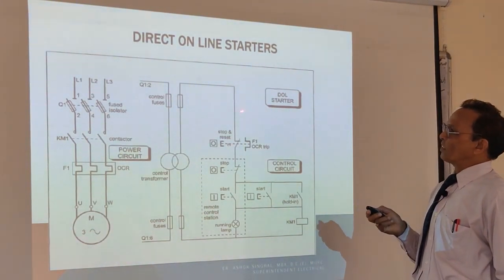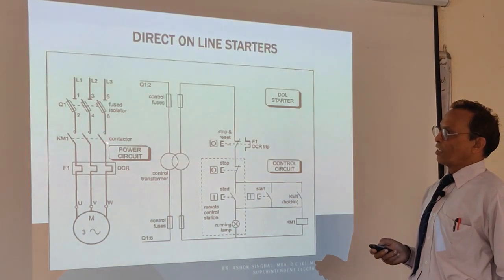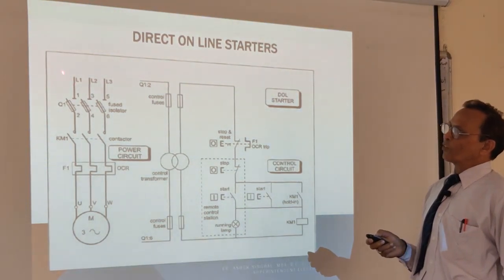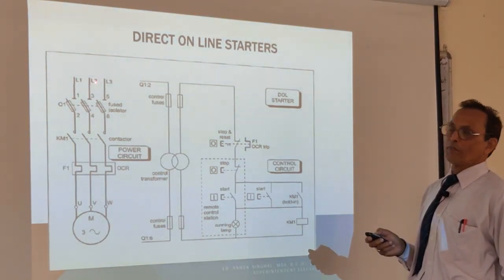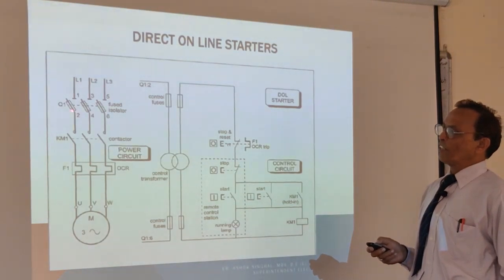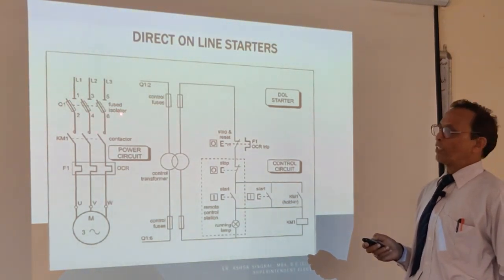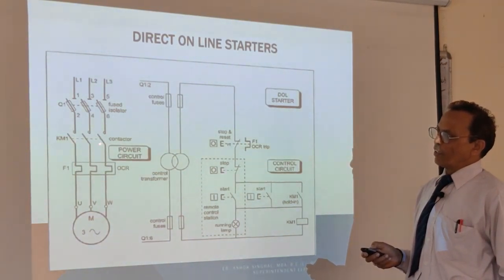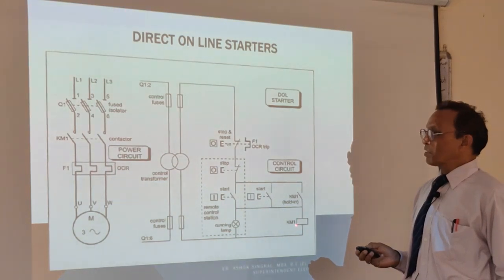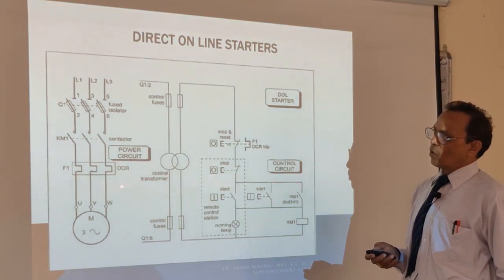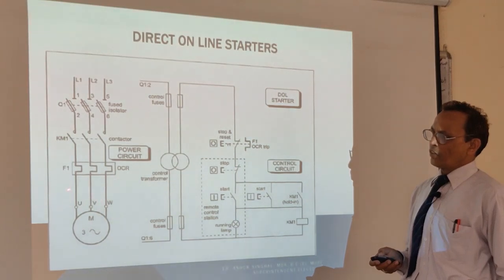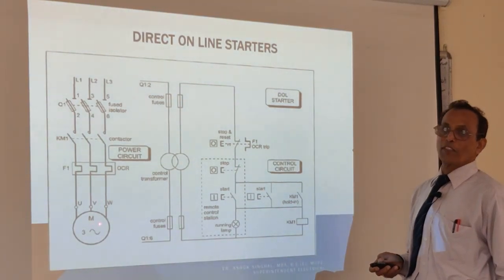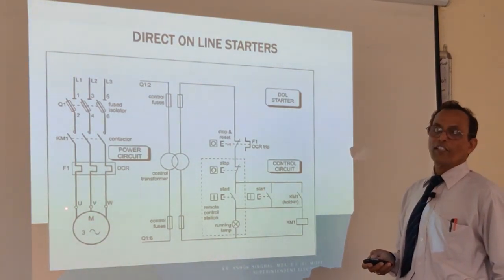Now when we look at this starter diagram, 440 volts is coming from the main switchboard. Then you have Q1, which is the fused isolator. Then you have all three phases and power is waiting at this point. This is KM1, the contactor coil. This is the overload relay or overcurrent relay. And then you have the three-phase 440 volt motor.